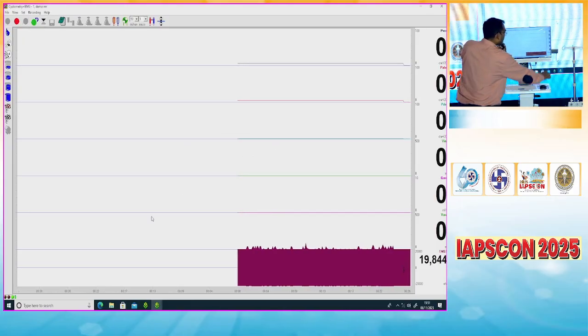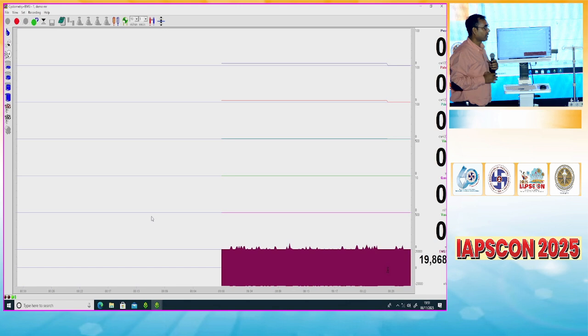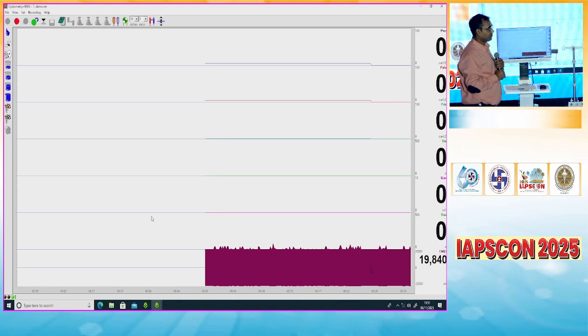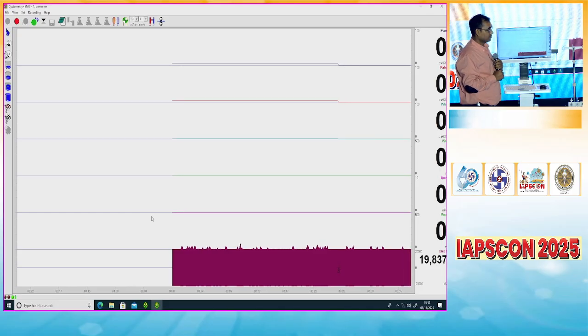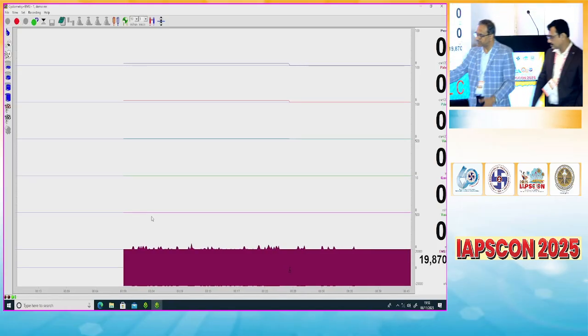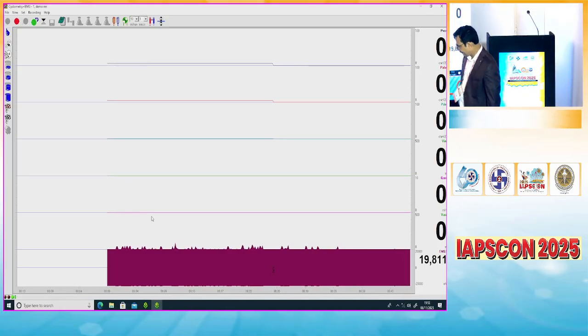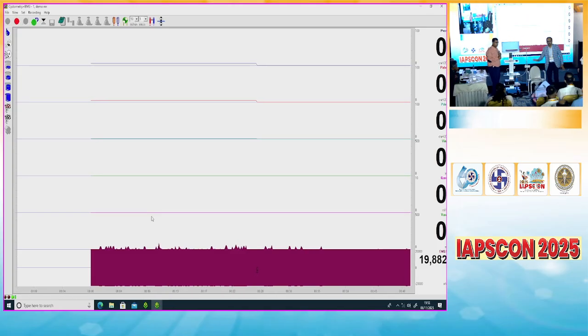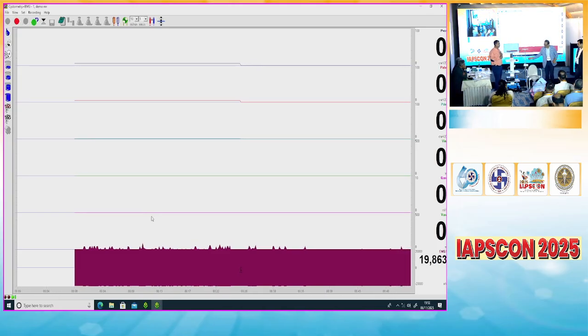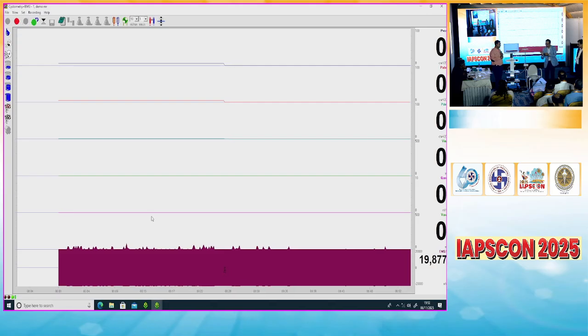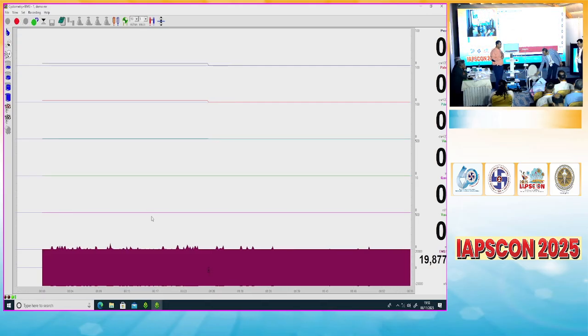So you can see here, this is the zeroing stage. What we normally do is bring the transducer to the pubic bone of the patient and do the zeroing. The machine adjusts accordingly. So this has to be level 0. If the child is lying down, we bring it to the pubic bone. Same if the child is sitting. Ideally, all these things have to be at the level of the patient. But the shortcut is to bring the transducer, that pole which is attached, here, and put 0. So the machine will record that as 0.